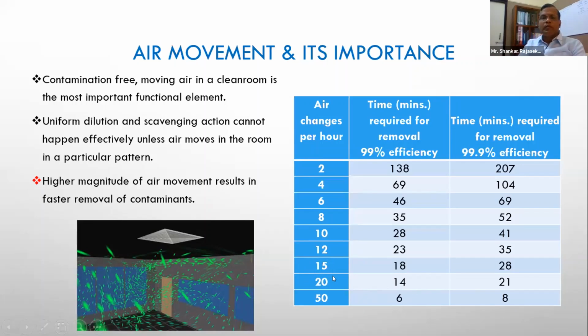At 20 air changes, it takes something about 14 minutes. And if you want 99.9% removal, at 20 air changes, it takes something like about 21 minutes. And this is more or less what we are looking at, around 20 minutes. If the theater can get ready for the next procedure, that's good enough. So the air changes are extremely important.